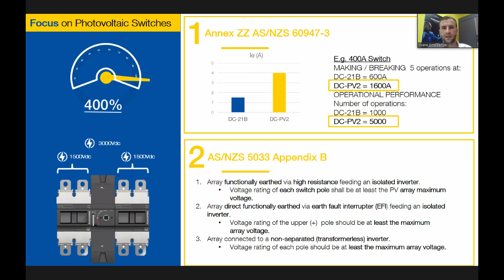However, in the Australian standard, under this specific configuration and the 2 mentioned below, you need to switch 1,500 volt DC on each polarity for a total of 3,000, preventing scenarios like double earth faults, which could lead to fire in extreme cases. So again, the Australian standards are really strict, and they are one level above the IEC standards when it comes to safety in photovoltaics.